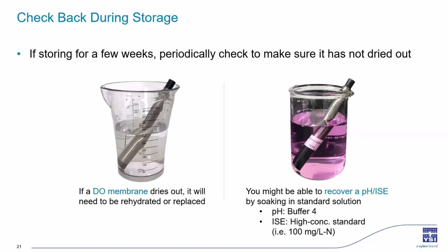If your calibration cup isn't fully sealed and the sensors do dry out, you still might be able to save them. If your DO sensor does dry out, you can go ahead and try to soak it in tap water overnight to rehydrate that membrane or the optical DO cap that's on it. This will usually work, but if not, you may still have to replace it. And then the same is going to go for your pH, ORP, or ISE sensors that dry out during short-term storage. You can try to rehydrate a pH sensor in pH 4 buffer and rehydrate the other ISEs in their standard solutions. Again, you may need to replace the sensor or the sensor tip if the data indicators are off or if the sensor isn't calibrating for you.